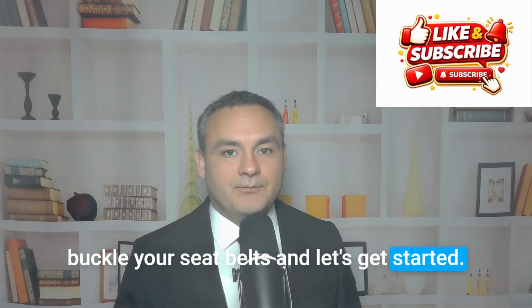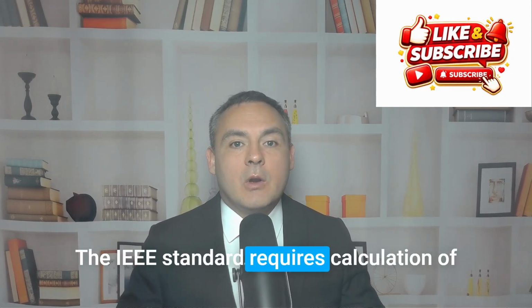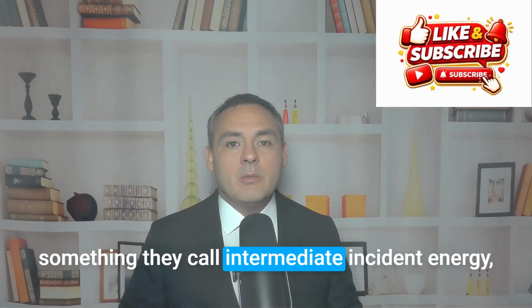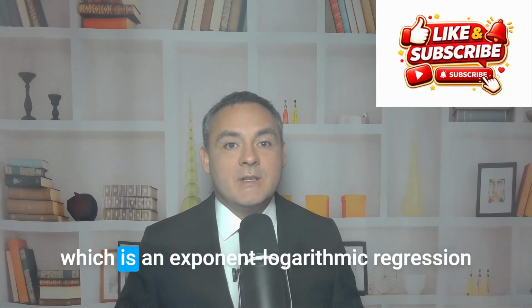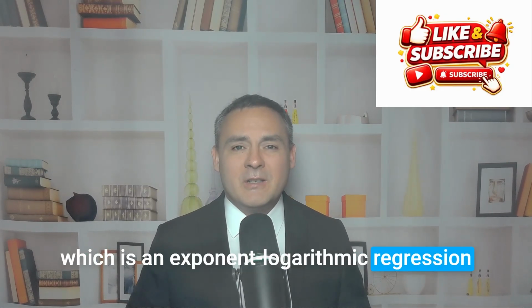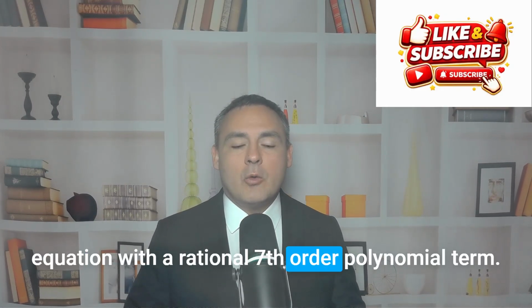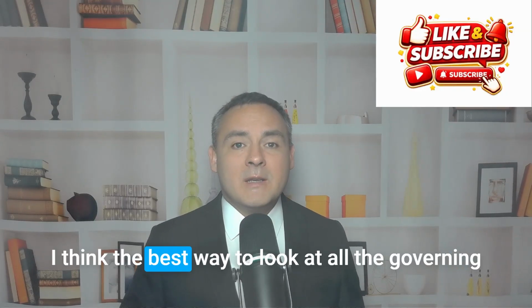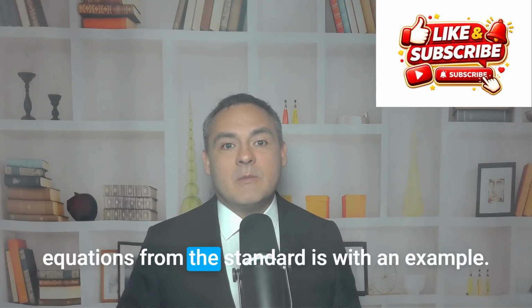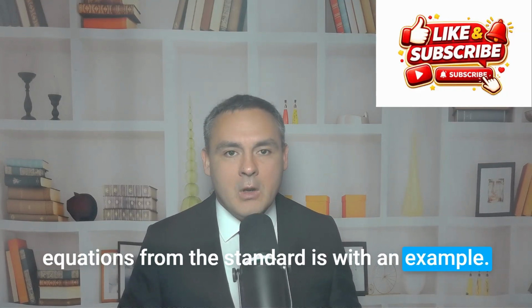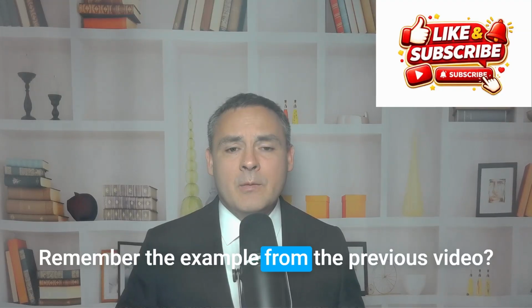The IEEE standard requires calculation of something they call intermediate incident energy, which is an exponent logarithmic regression equation with a rational 7th order polynomial term. I think the best way to look at all the governing equations from the standard is with an example. Remember the example from the previous video.